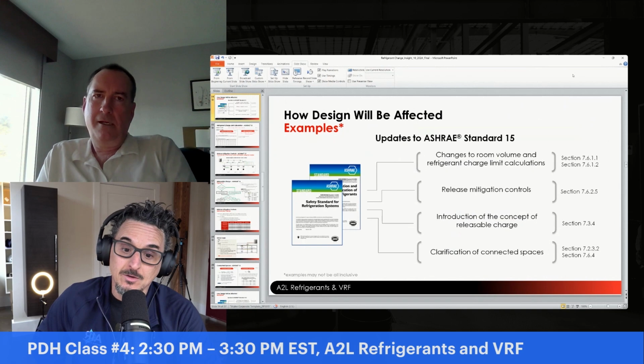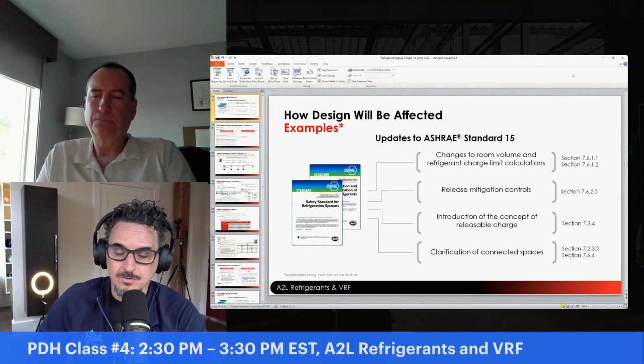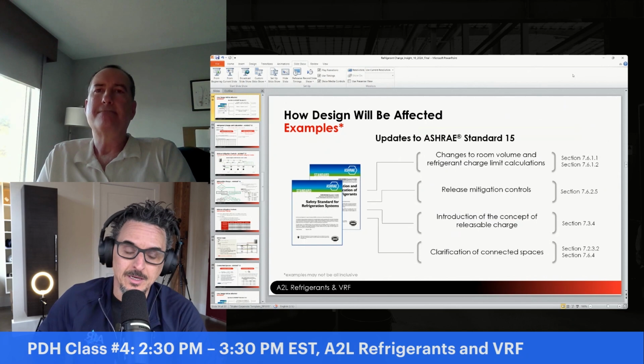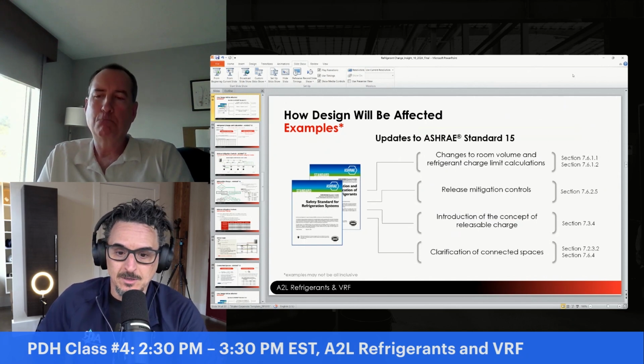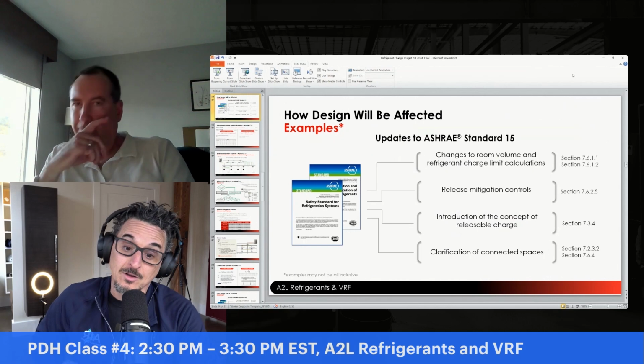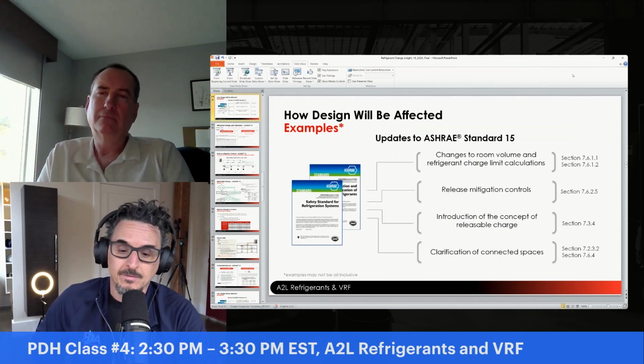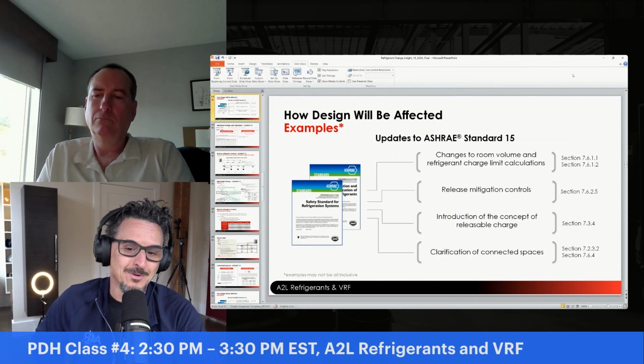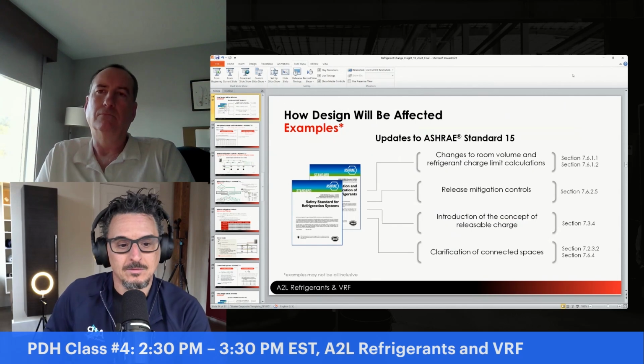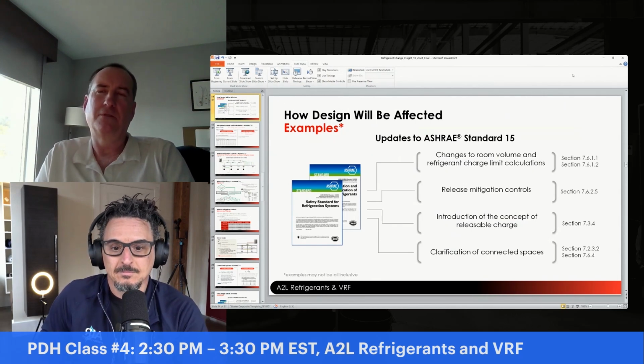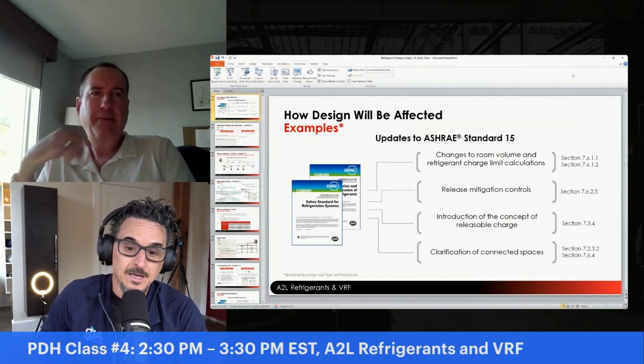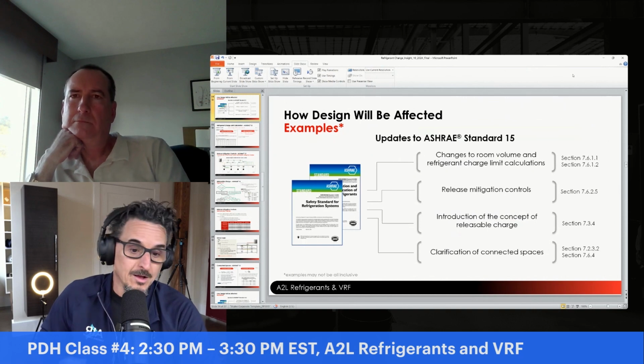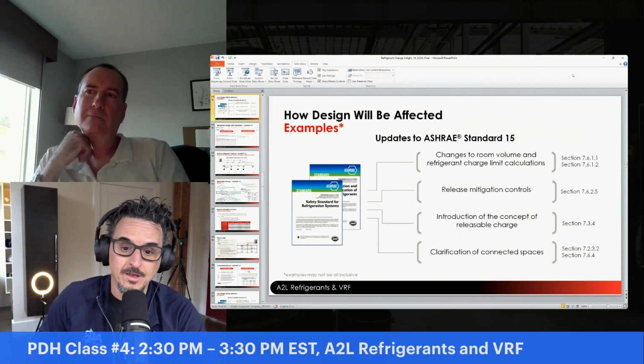The UL is what you as manufacturers have to adhere to in terms of construction of the equipment and compliance, and that's one of the major things with A2Ls - it's a different UL requirement. That's why you can't just swap it, because the A2L requires a different UL rating. They're not just two different versions of the same thing, there are differences behind them. We get asked all the time if an owner has an older piece of equipment, can I just take all the refrigerant out, clean it up, change a few components, and put this in? And I'm like, no, that violates the UL and you don't want to do that.